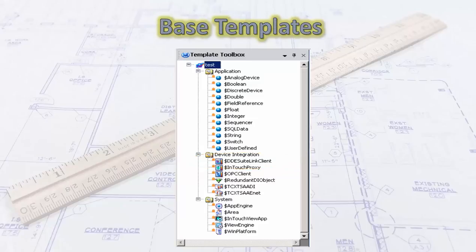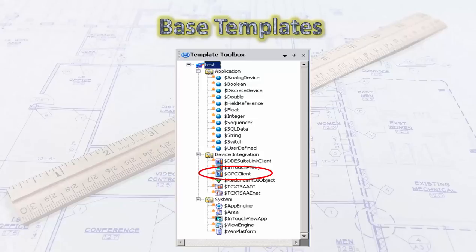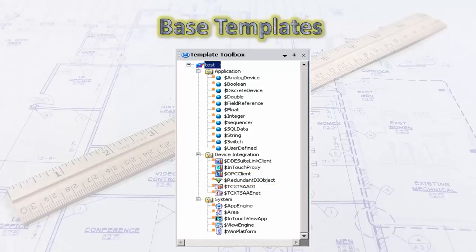InTouch Proxy allows you to communicate with InTouch applications inside the galaxy. If you have a server like Allen-Bradley and you're using RSLinx — which is an OPC server — you can take a generic OPC client and communicate with that OPC server. So you can use the OPC client to communicate with RSLinx. Redundant DI is for use in redundant applications where you need two platforms running separate clients that need a failover, and that's what it's used for.